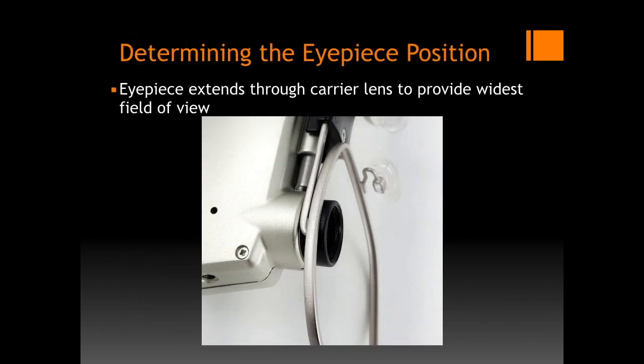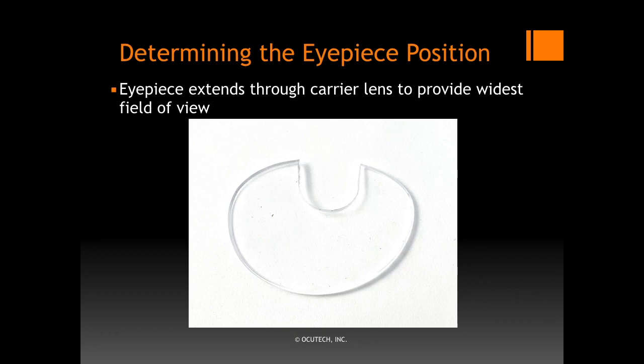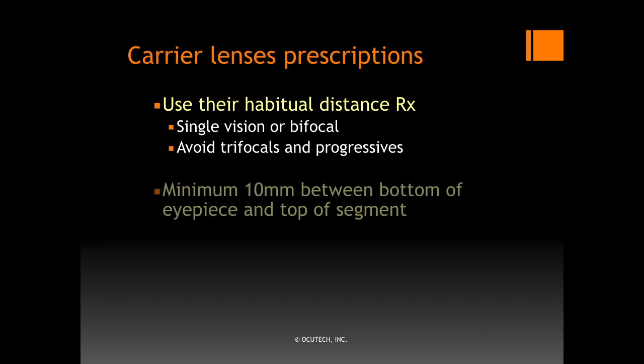The Falcon eyepiece extends through the carrier lens to provide the widest field of view possible. When ordering the system, the eyepiece position must be specified as the carrier lens will be slotted to allow the eyepiece to pass through. Once you have confirmed the ideal position for the eyepiece, use a millimeter rule to measure from the center of the bridge to the center of the eyepiece to specify the proper eyepiece position. The slot is made slightly oversized to allow for fine tuning at the dispensing visit. We recommend prescribing carrier lenses consistent with what your patient normally wears. Consider a bifocal if they normally wear one. We suggest avoiding trifocals and progressives. Be certain to provide at least 10 millimeters from the bottom of the eyepiece to the top of the bifocal segment. OcuTech's frame spec sheet lists suggested bifocal segment heights for all of its frames. If you are not certain what to specify, just write 'standard' and OcuTech's order department will position it appropriately.